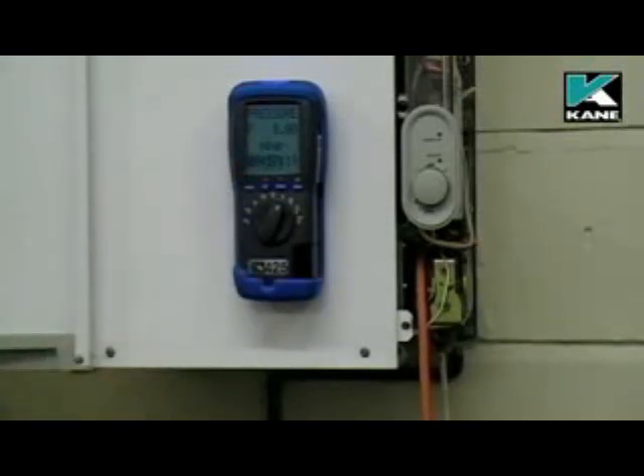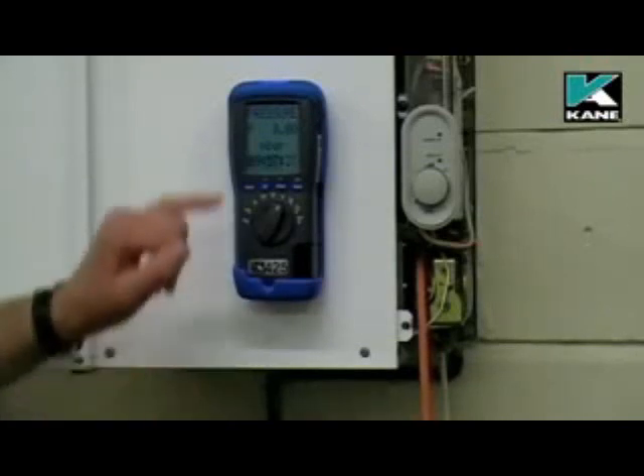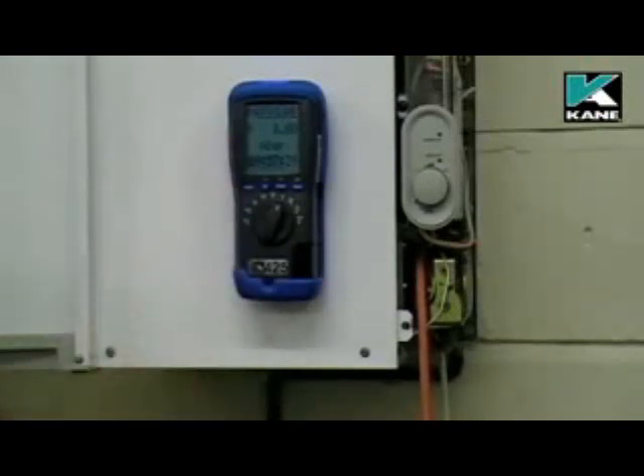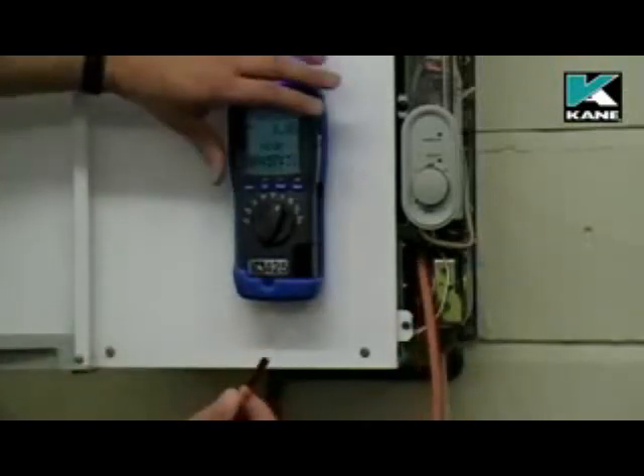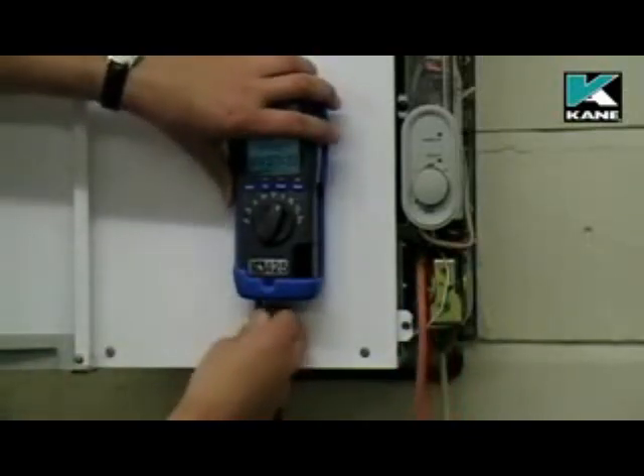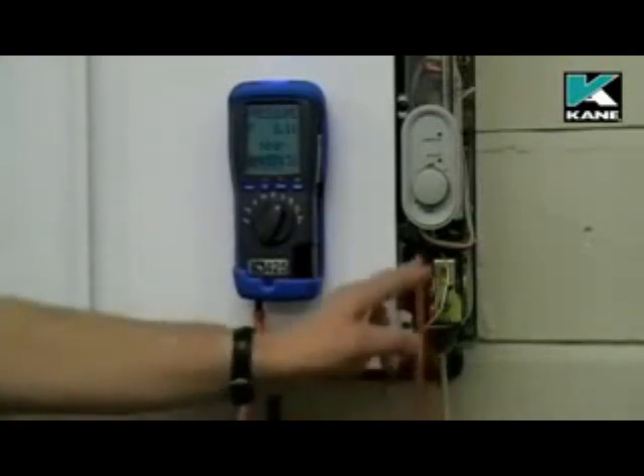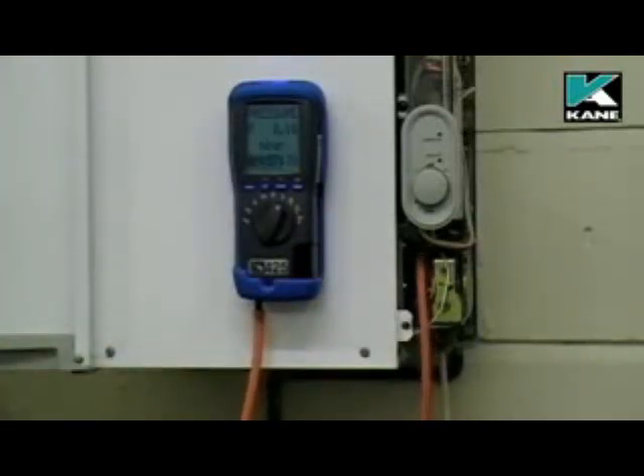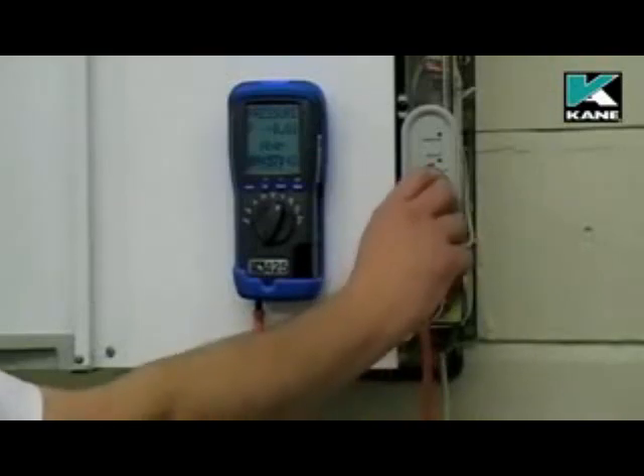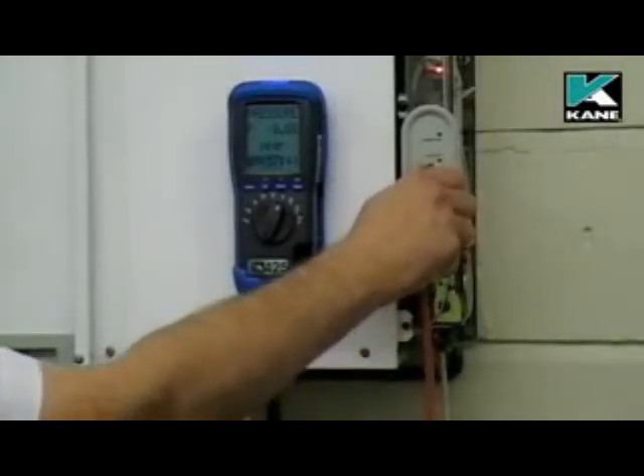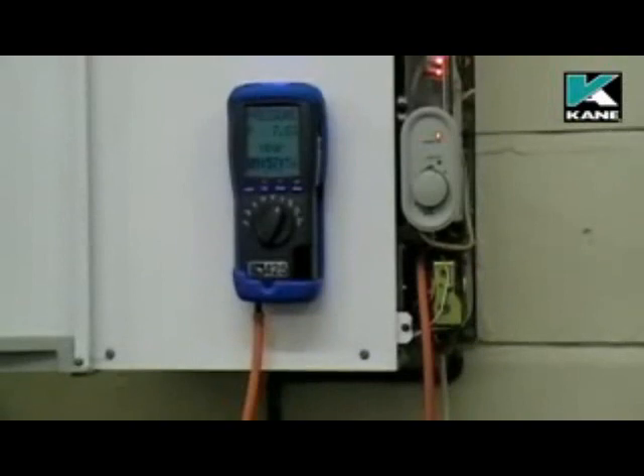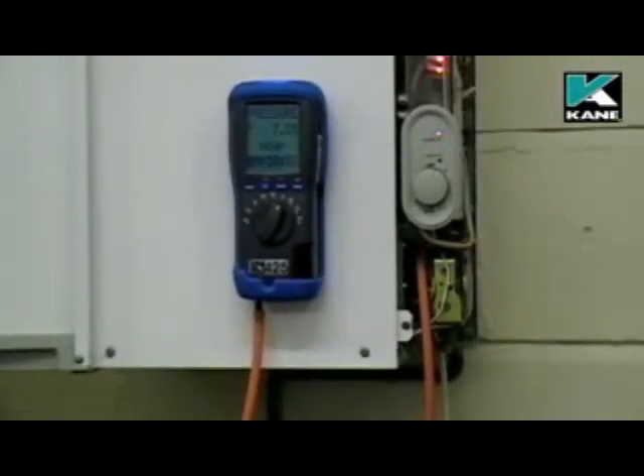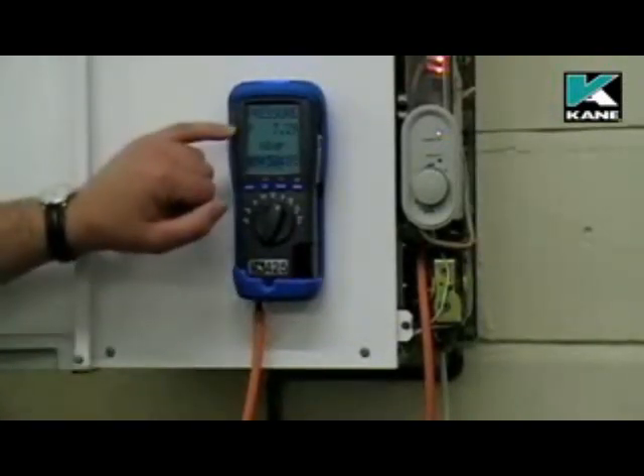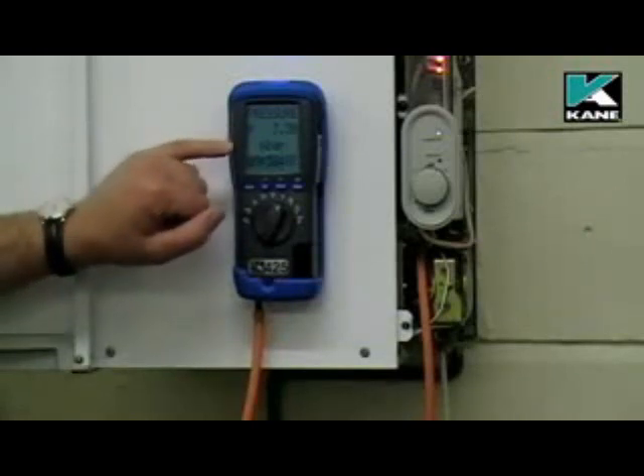What we're going to do is actually set a burner pressure as per the manufacturer's instructions. So we've zeroed the pressure sensor. I can now connect the hose to P1. It's already connected to the boiler. Now I can fire the boiler. Just wait for the pressure to stabilise. So here we've got a pressure of 7.3 millibars.